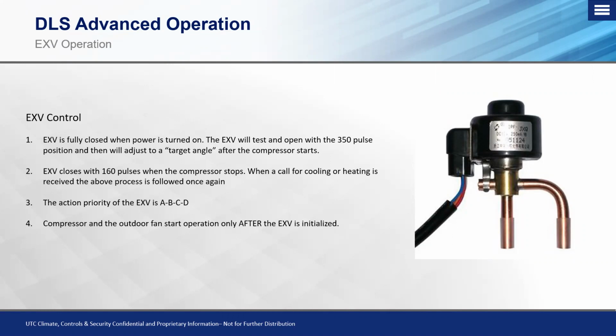The compressor and the outdoor fan start their operation only after the EXV has initialized. If for some odd reason that EXV is going through its test function and fails, or it's not pulsing at all, that compressor and outdoor fan motor will not start. That's essentially a safety control to verify that the valve can open. The board receives that command, okay, it's open, and then it adjusts the compressor and outdoor fan speed as needed when it starts up, and the valve pulses open or closed, depending on how much refrigerant needs to be fed into that particular indoor unit.